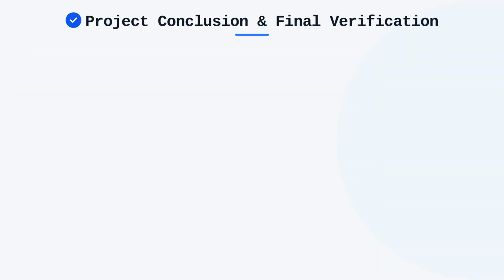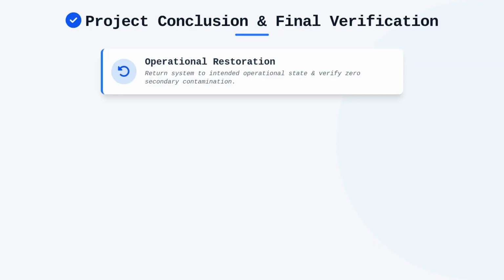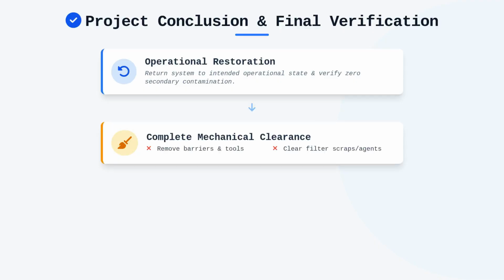Finally, the project concludes only when the system has been returned to its intended operational state and verified to be free of any secondary contamination. You must ensure that all tools, containment barriers, and secondary waste materials have been completely removed from the mechanical space to avoid introducing new particulate matter into the system. Leaving behind debris, such as filter media scraps or cleaning agents, is a common pitfall that can lead to recontamination of the supply air almost immediately after startup.